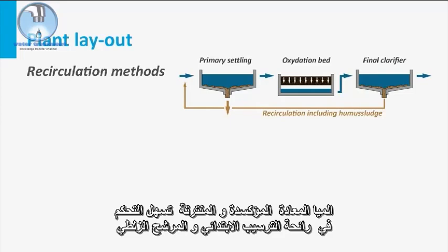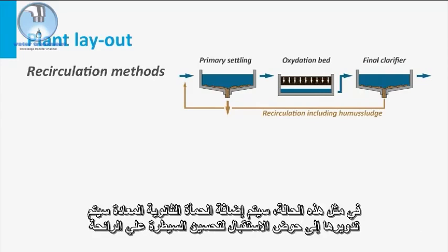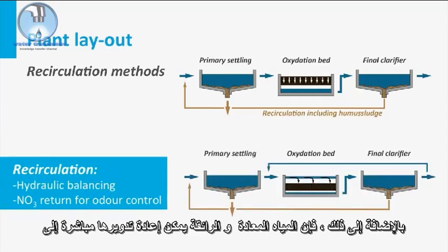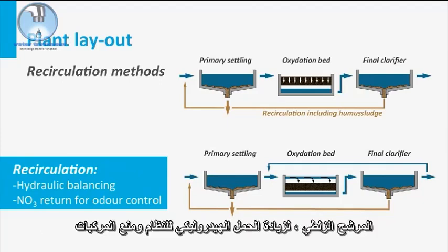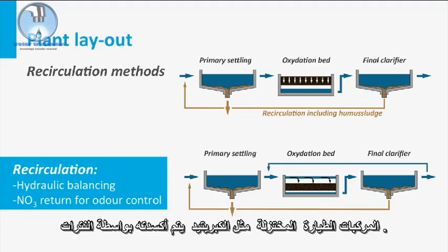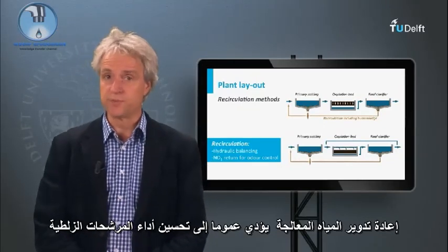The oxidized and nitrified effluent facilitates odor control in the primary clarifier and the trickling filter. When connected to a gravity sewer, the primary clarifier is preceded by an influent reception basin. In such case, the recycled secondary sludge will be added to the reception basin for enhanced odor control. Additionally, the nitrified and clarified effluent might be directly recycled to the trickling filter to increase the hydraulic loading to the system and to prevent volatile odorous compounds escaping the filter system. Reduced volatile compounds such as sulfides are then oxidized by nitrate. Effluent recirculation generally leads to improved process performance of the trickling filter.